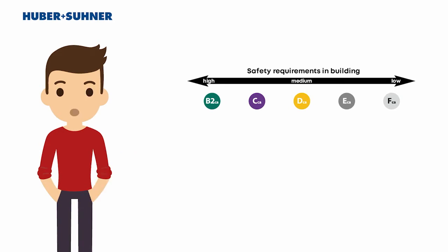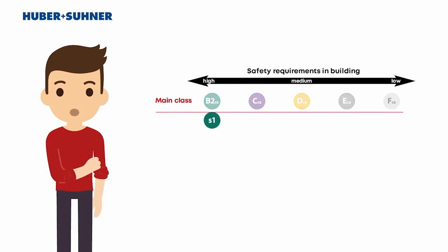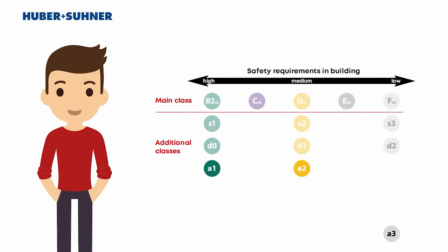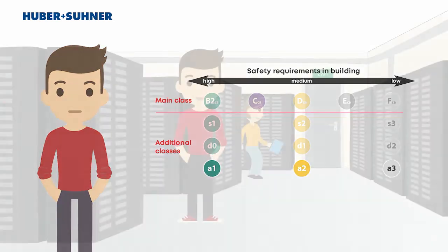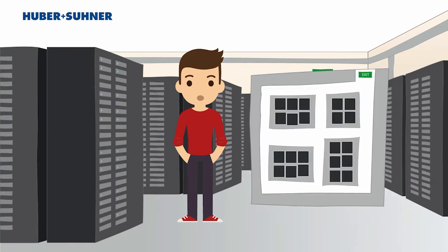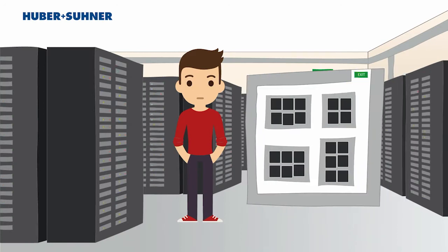With CA here simply standing for cable. The fire safety requirements don't just cover heat release. There are also classifications for smoke emission, represented by the letter S, flaming drops by the letter D, and acidity by the letter A. I sometimes wonder what would happen if a fire started in the cable canal near the exit of a data center I was working in.